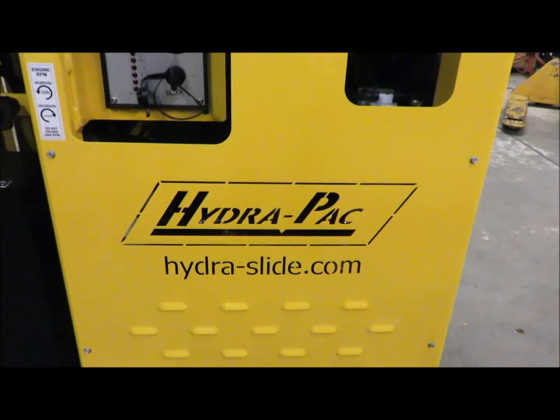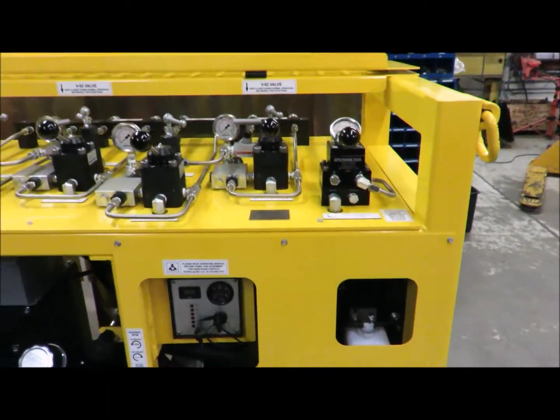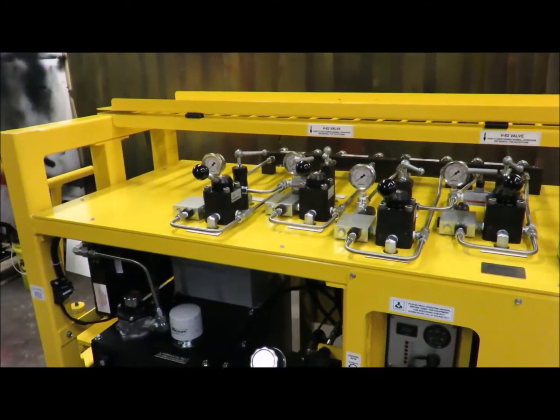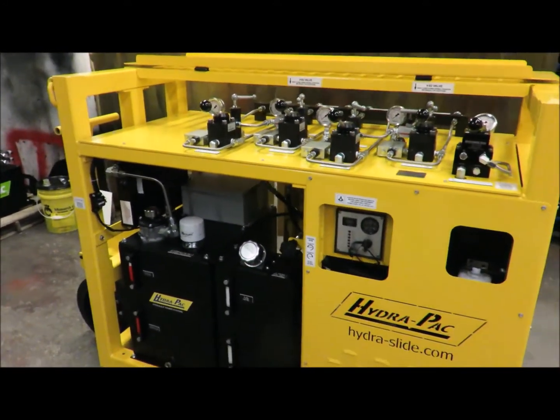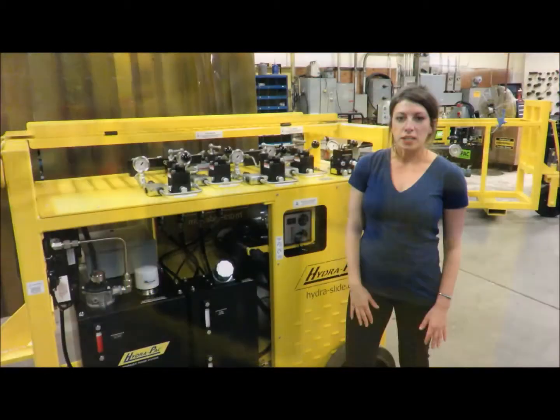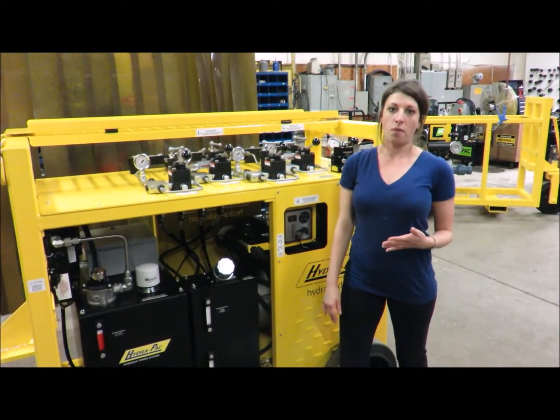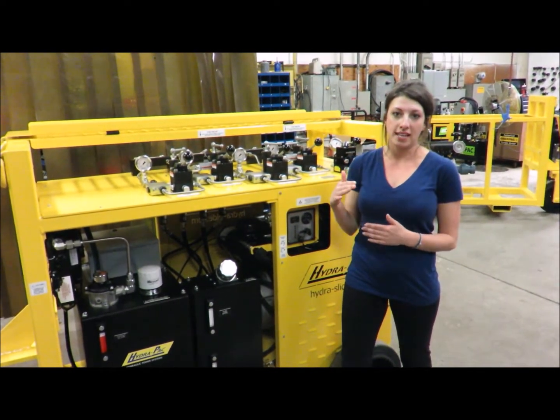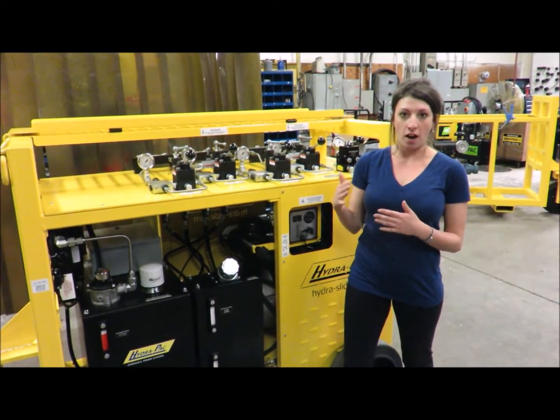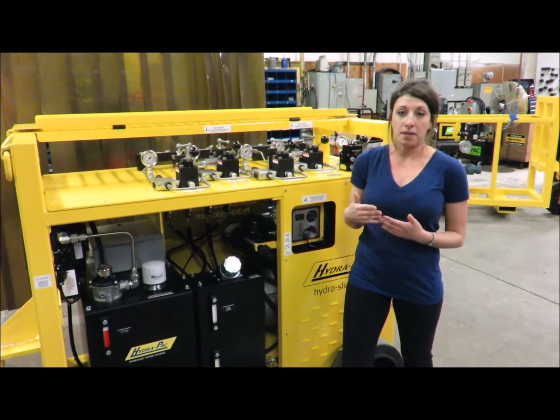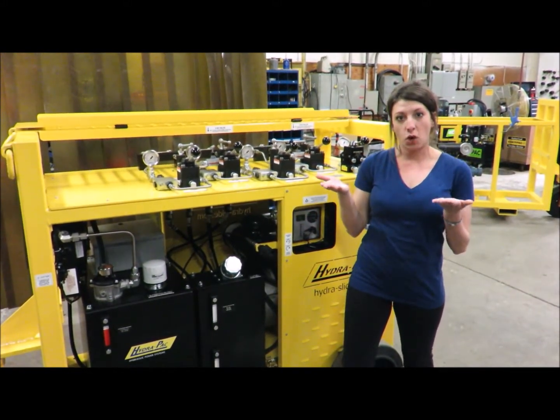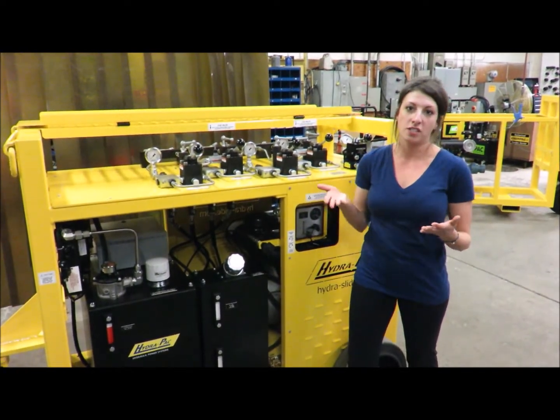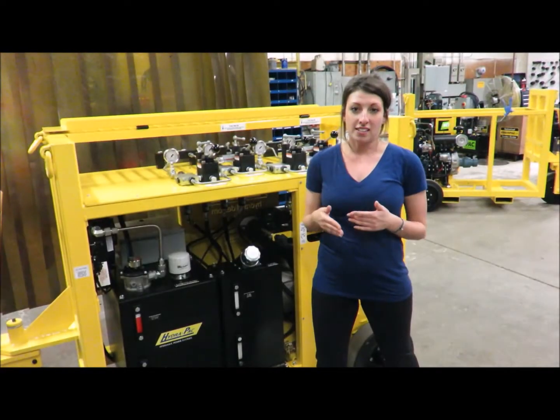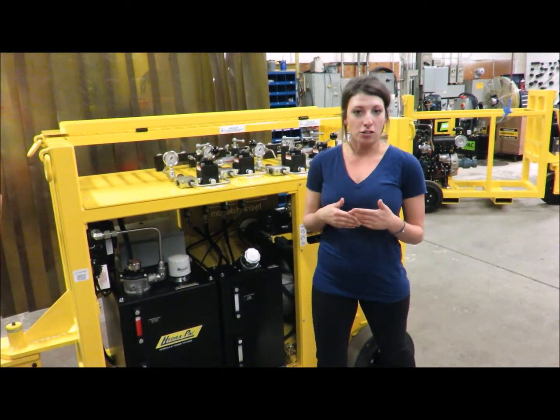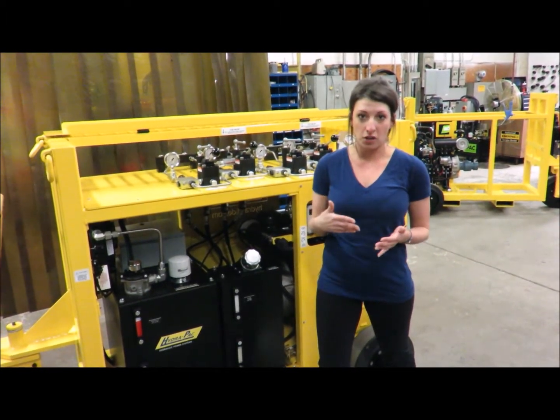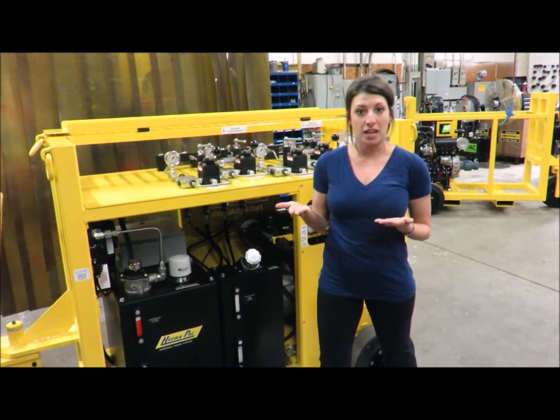Our Hydra-Pac synchronous power units are designed with multiple but independent oil circuits. These circuits are not connected to each other and will give equal flow to each line regardless of the pressure in that circuit. If we use the same example of jacking a transformer on 4 points, each of your cylinders is going to extend and retract at the same rate, regardless of an offset center of gravity on your load. What that means is that your load is always going to raise and lower at the same rate, regardless of different pressures seen on each circuit. This method is not only faster than end-to-end jacking, it also reduces risk of damage to the load, other equipment, and it reduces the chances of the load becoming unstable at any point.